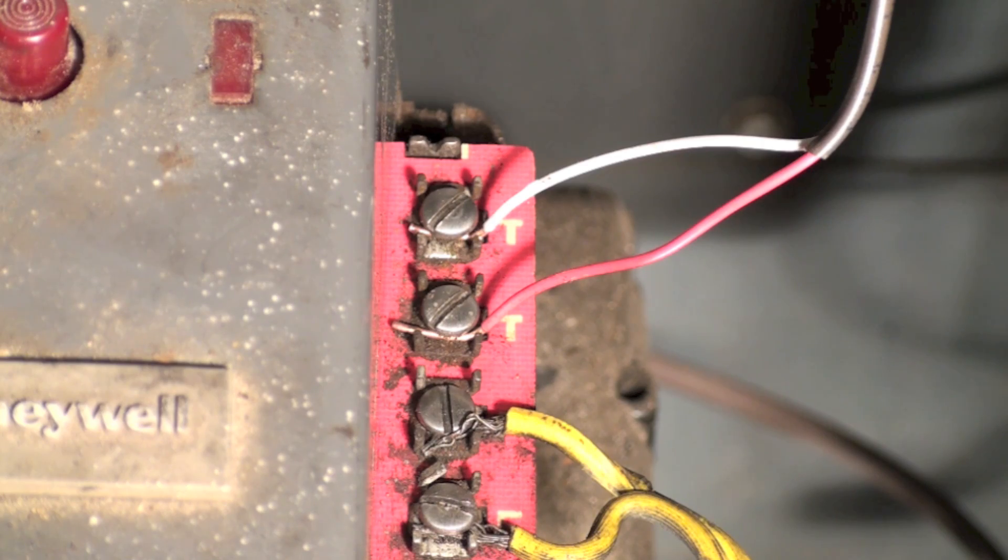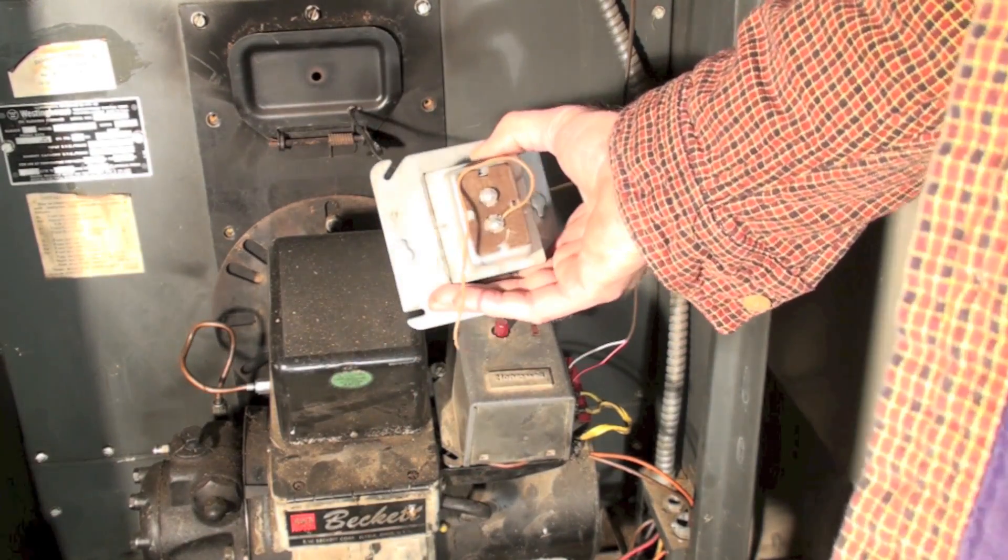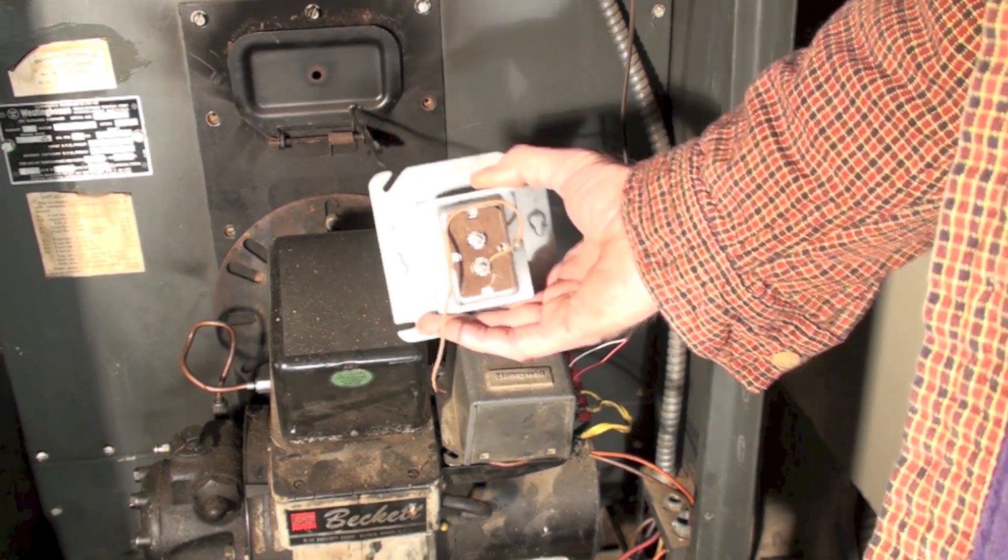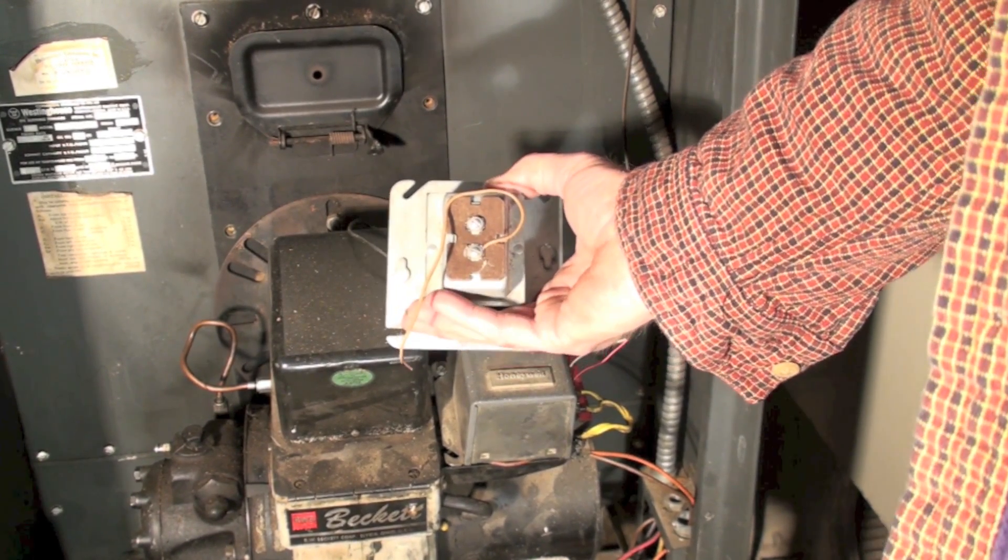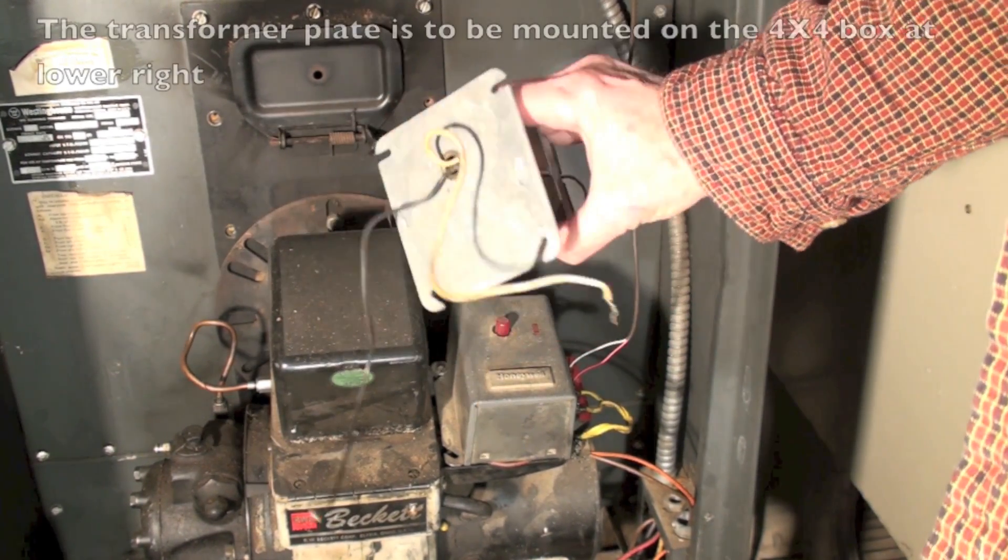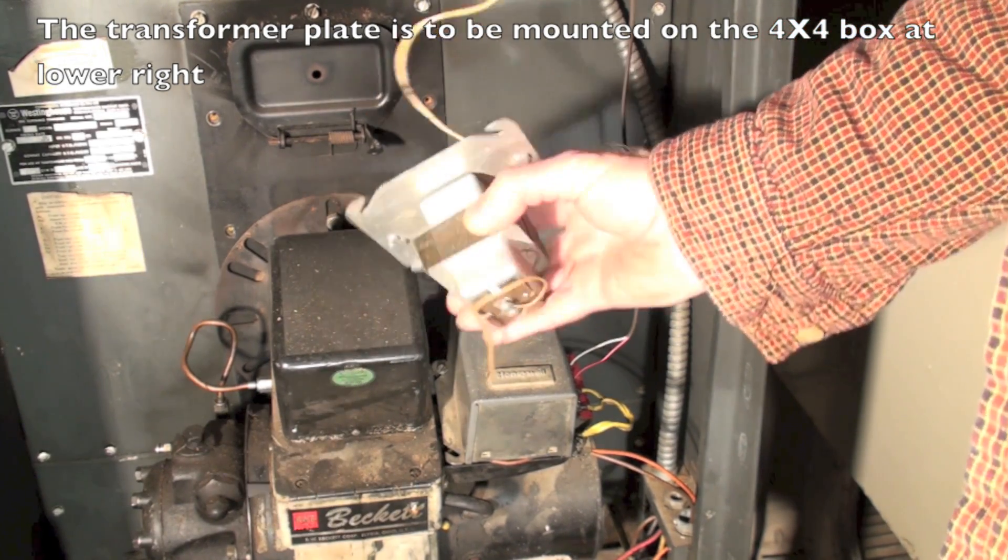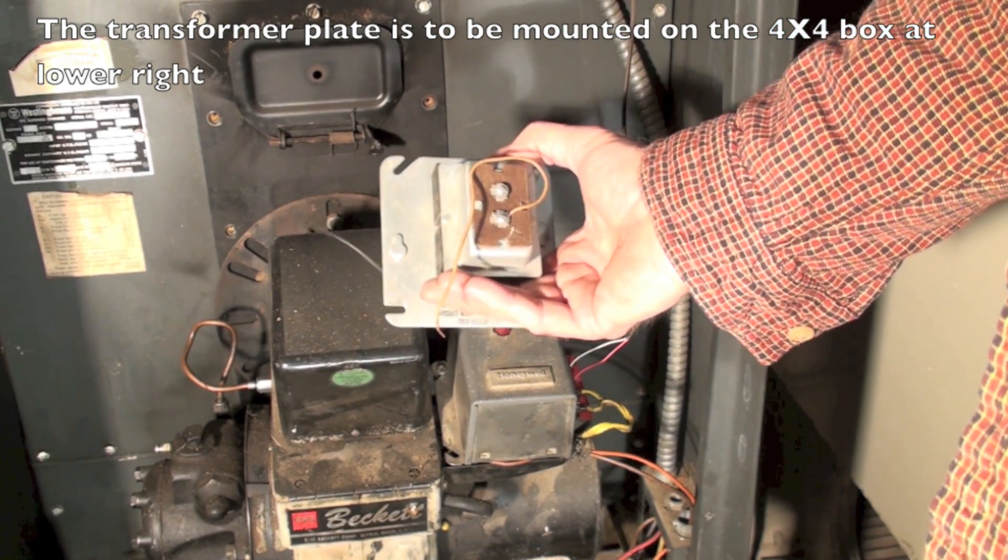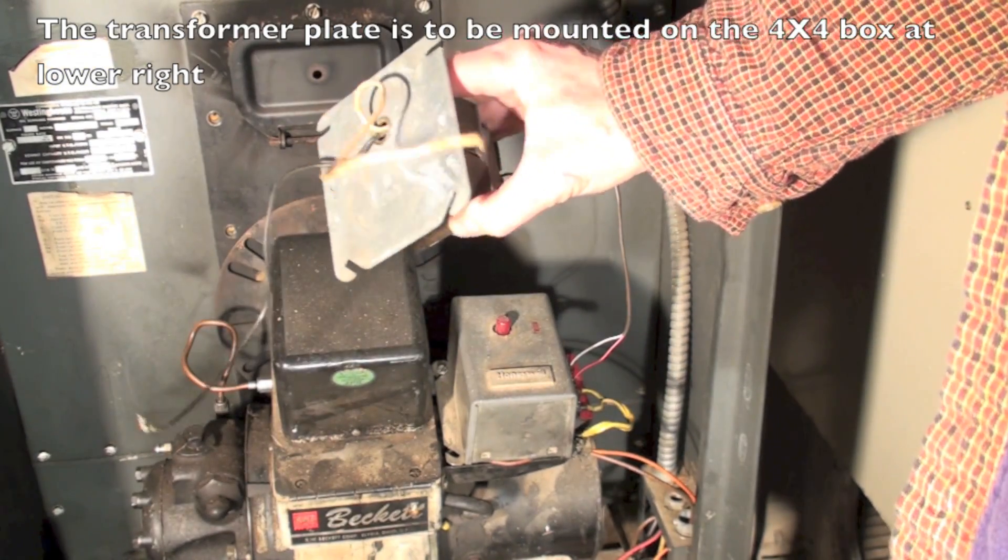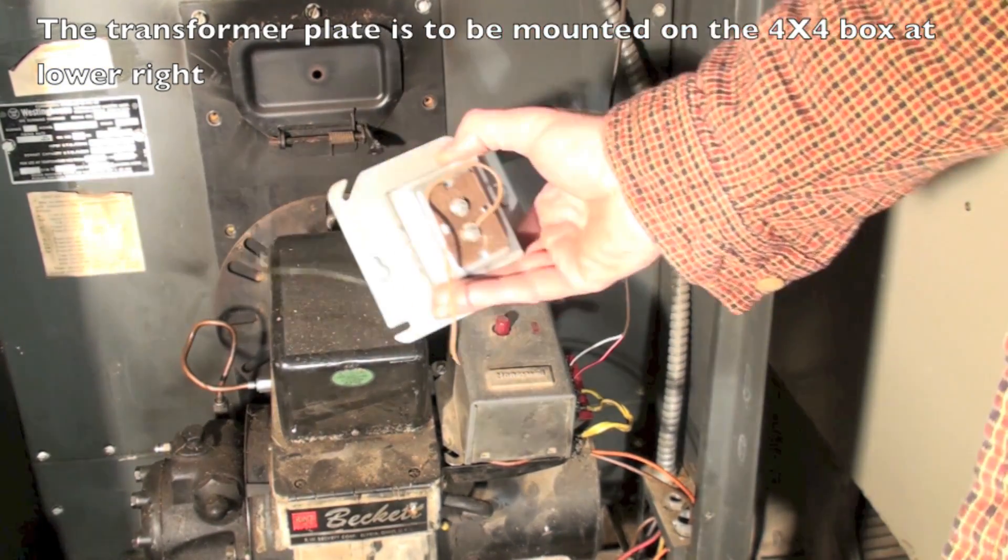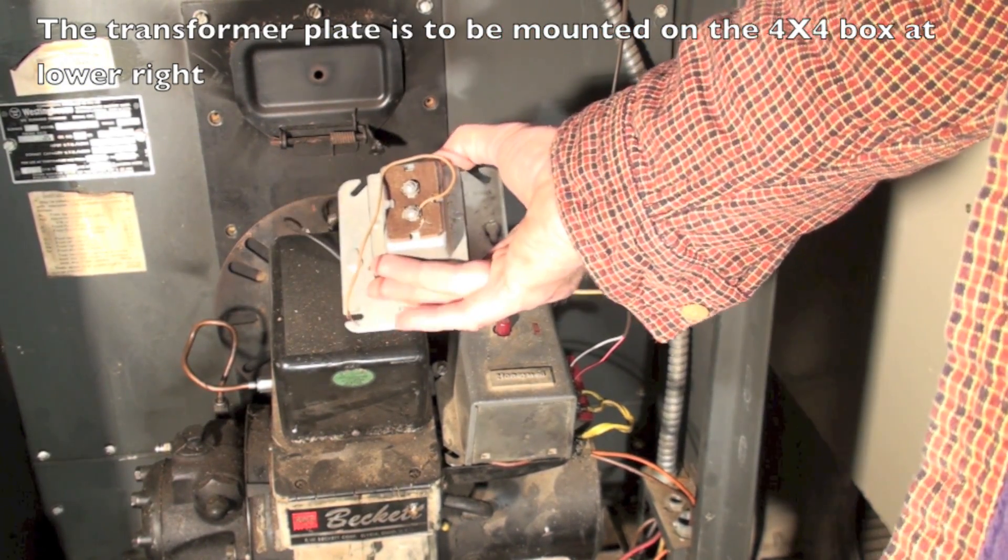This is going to be one way of solving this problem. I'm just taking a transformer that's mounted on a four by four plate, and I'm going to put it on the furnace so there's power to it. This is the 120 volt side all the time, and I'll have 24 volts coming out of there.